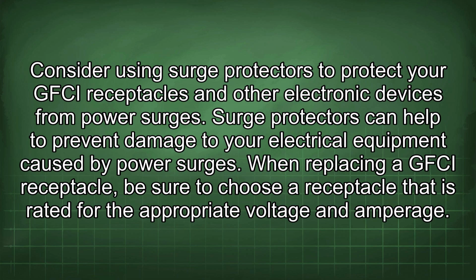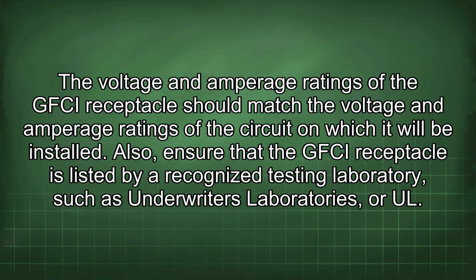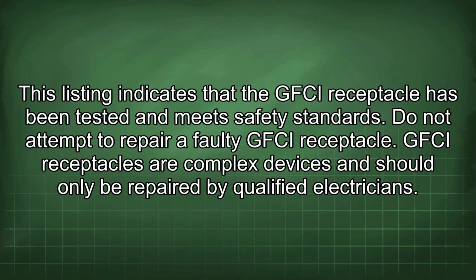When replacing a GFCI receptacle, be sure to choose a receptacle that is rated for the appropriate voltage and amperage. The voltage and amperage ratings of the GFCI receptacle should match the voltage and amperage ratings of the circuit on which it will be installed. Also, ensure that the GFCI receptacle is listed by a recognized testing laboratory, such as Underwriters Laboratories, or UL. This listing indicates that the GFCI receptacle has been tested to meet safety standards.